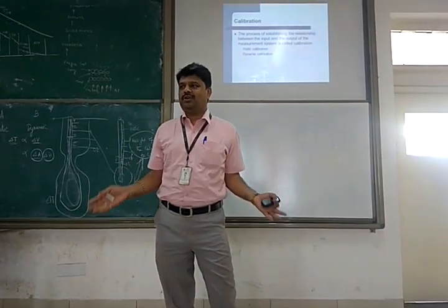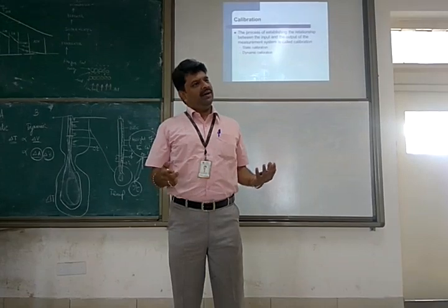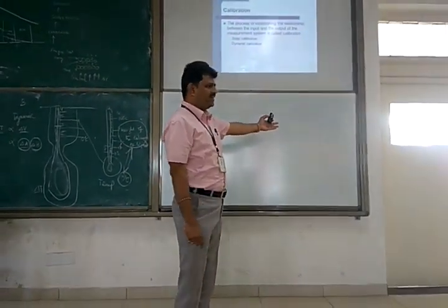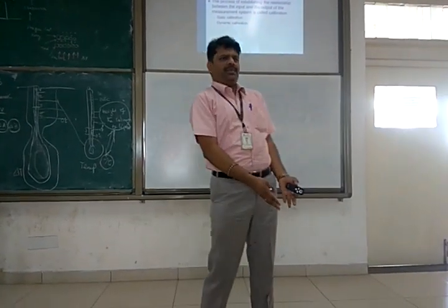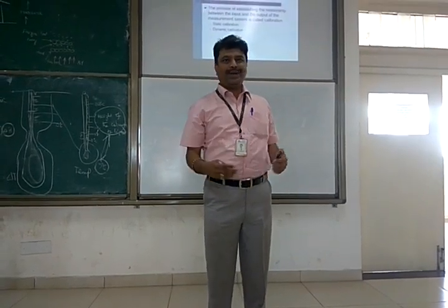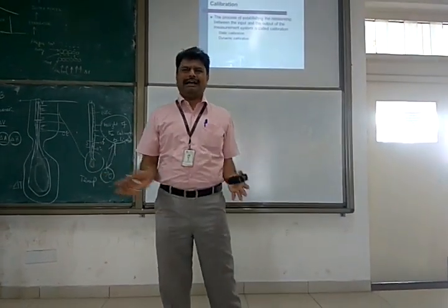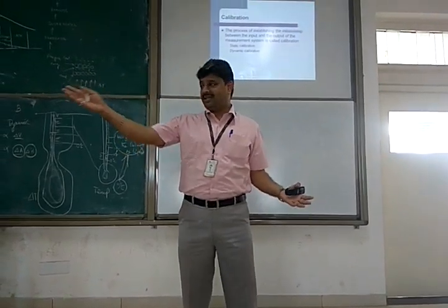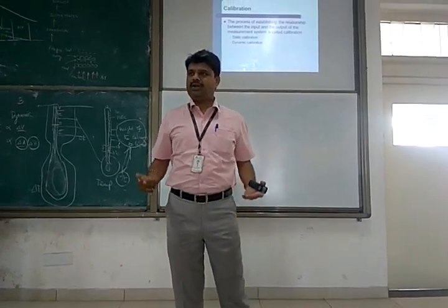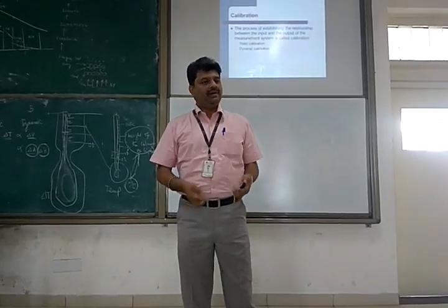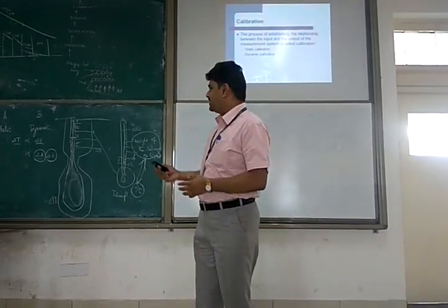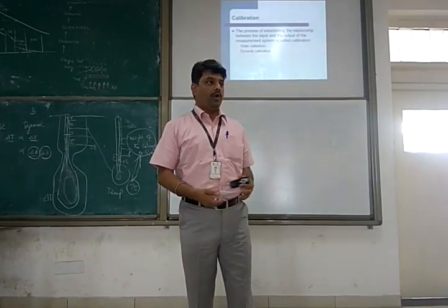Nothing is kept under control. You simply allow everything to vary. You can bring it to your factory. There may be some furnace there. There may be some dust-producing melting process going on. You want to use it here, probably a little far away from the furnace. Of course, not very close to it. There is humidity too. Sometimes there is a spraying unit and humidity is high. That's a usual thing in many factories. Can I use this inside the factory? Yes, without any trouble you will be able to use it, provided it is dynamically calibrated. It will be more rugged.